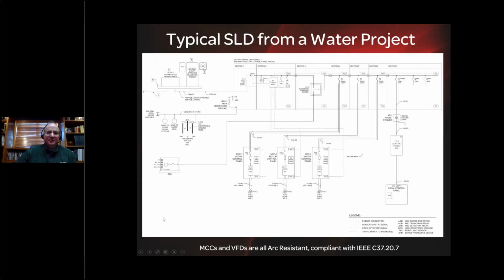So this is a typical single line diagram from one of our water projects that we did recently. And on this project, it was specified that the motor control centers, which you see that there's only one big MCC in this project, in the upper right-hand corner, would be arc resistant along with the transfer switch. And the downstream variable frequency drives would be arc resistant as well.